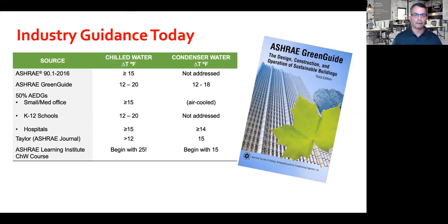your climate. All of the advanced energy design guides that include chilled water systems recommend chilled water temperature differences significantly higher than the older methods. For the condenser side, the ASHRAE Green Guide and advanced energy design guides recommend a 12 to 18-degree delta T. And finally, the ASHRAE Learning Institute course on chilled water systems recommends beginning with a 25-degree chilled water delta T and 15-degree condenser water.